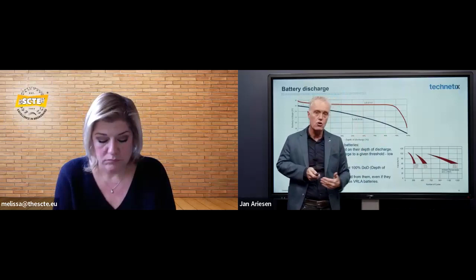The pros of DC powering: we have low power consumption, and less stress in the network because with 50 Hertz AC you have 100 current peaks per second. With DC you have a constant flow, and therefore less stress in the network, and therefore better MTBF. You also have a power factor of 1, so you don't have to worry about the power factor of your amplifiers like you do in AC.